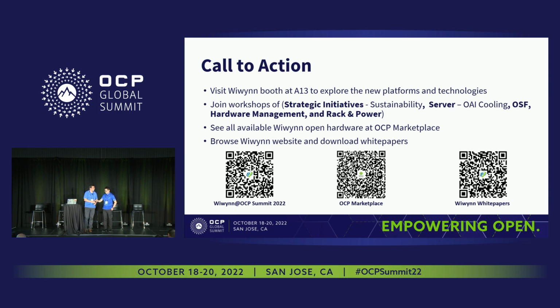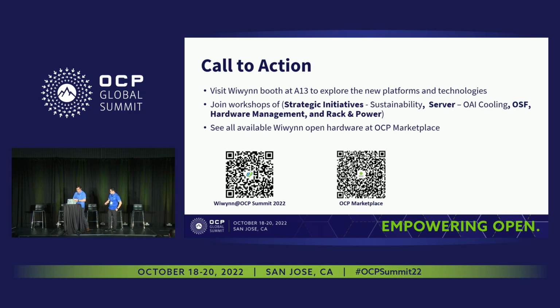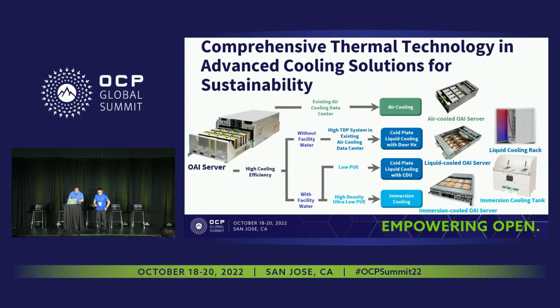Okay, thank you. I'd like to use this page to explain the application for different cooling solutions. For existing air-cooled data centers, most users would choose the air cooling solution. For existing air-cooled data centers without facility water, but wanting to solve high power problems, they can use the cold plate solution with a door heat exchanger. If the user has facility water in the rack room, they can use the cold plate to get a lower PUE for high-power chips, and also use immersion cooling to get much higher cooling capacity with an even lower PUE.